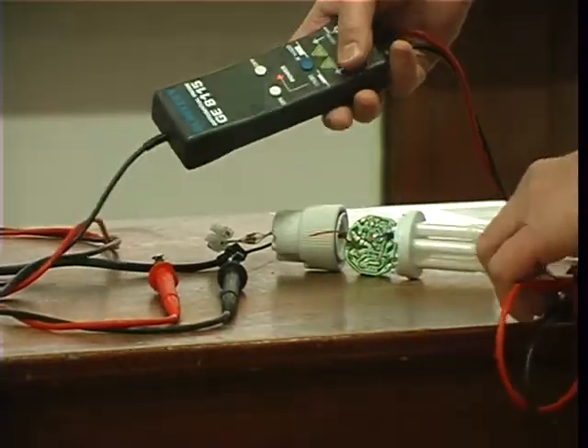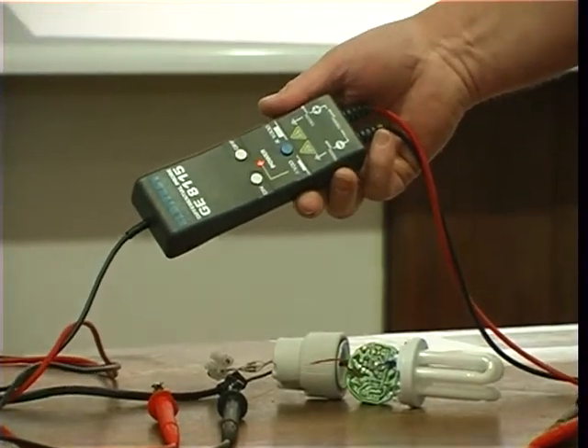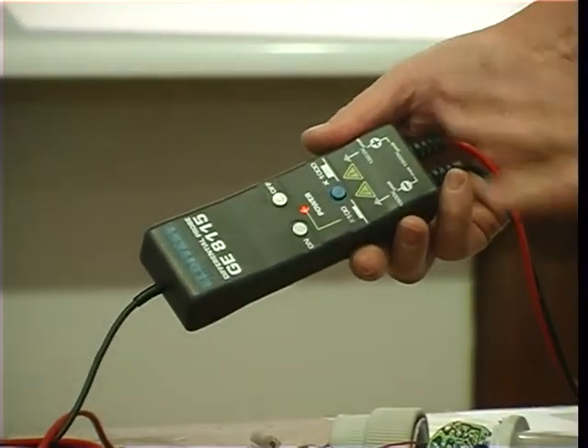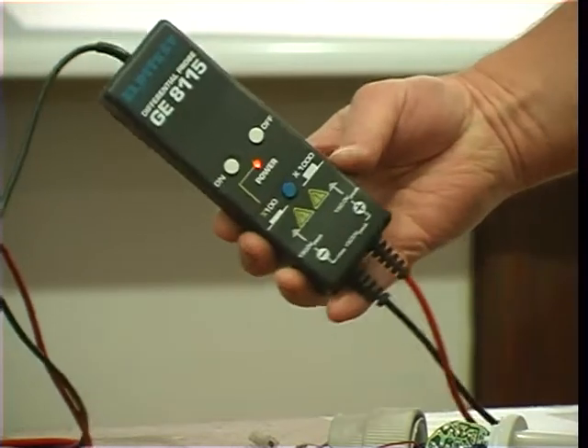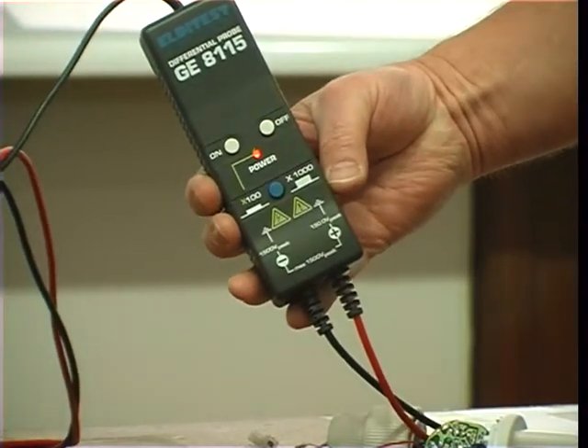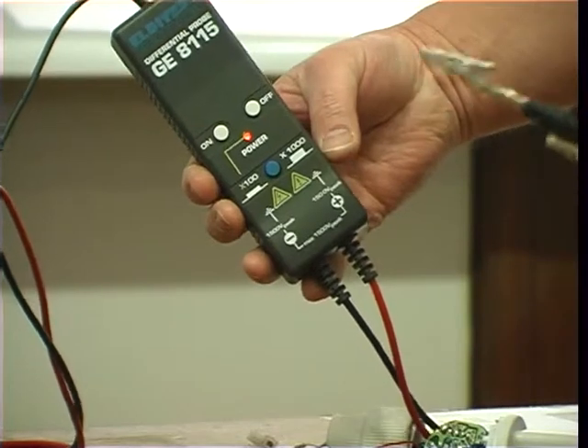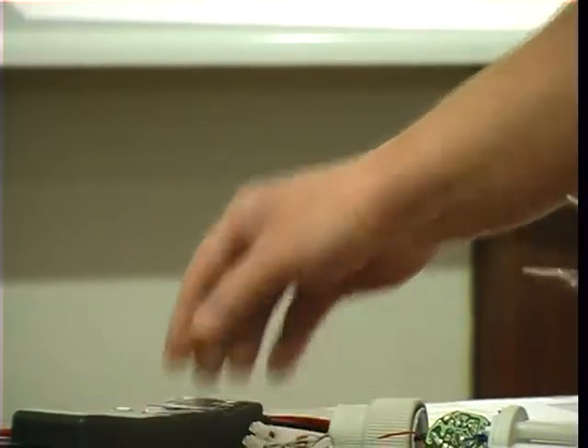Right, we're going to measure voltage, we're going to use these rather special differential probes, this is mains voltage, don't do this at home, it's very dangerous. These differential probes are designed especially for this type of activity so there's no earth, there's no ground and we can just connect across so I can put those on my voltage here.